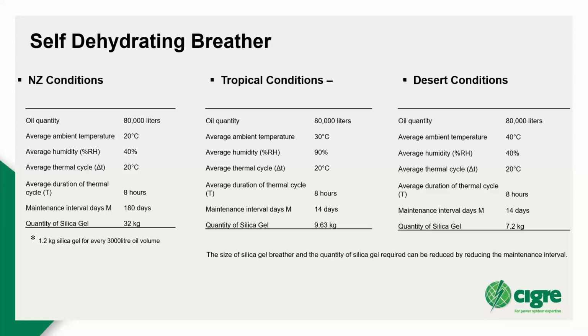And that is exactly what the self-dehydrating breather, or smart breather, or maintenance-free breather, is doing. In this example, I took some New Zealand conditions, and I say I will maintain my breather every 6 months. If I do that, for 80,000 liters I need roughly 32 kgs, which translates to almost 1.2 kg of silica gel for every 3,000 liters of oil volume.